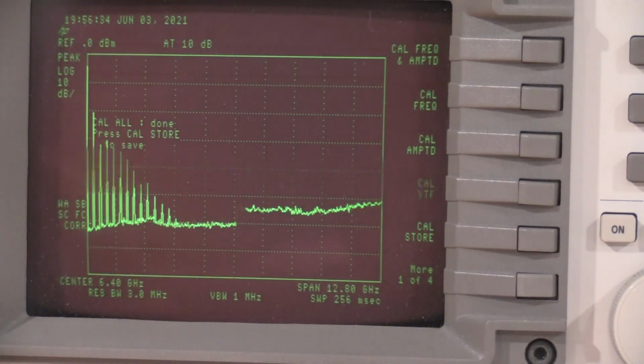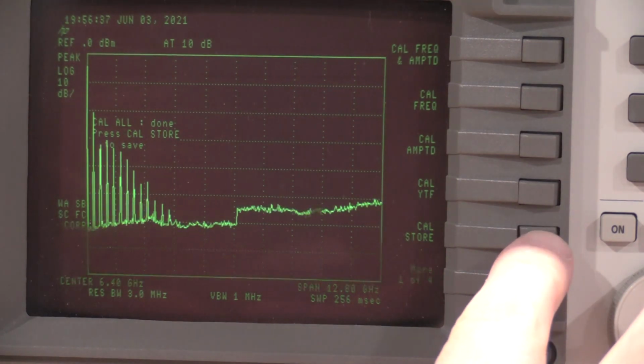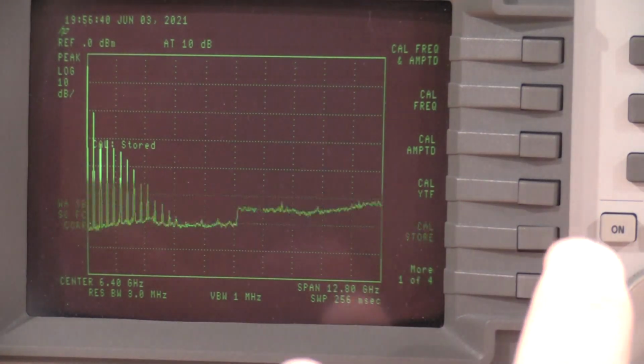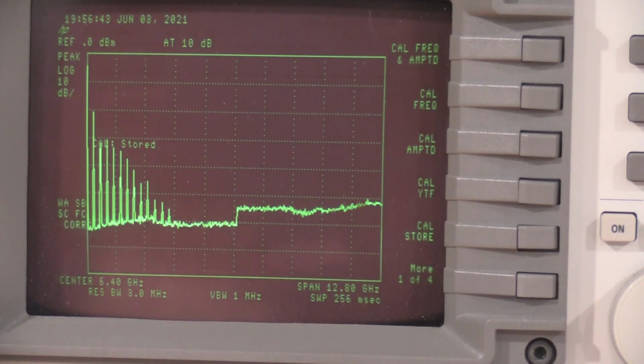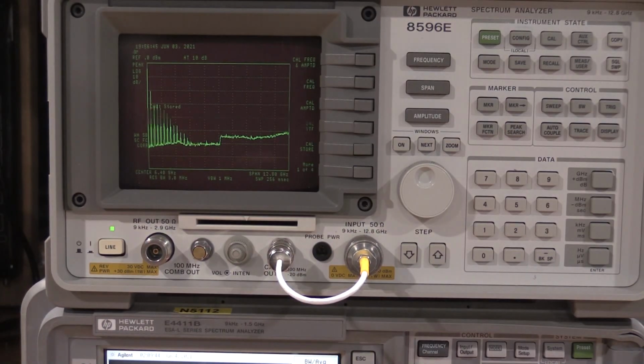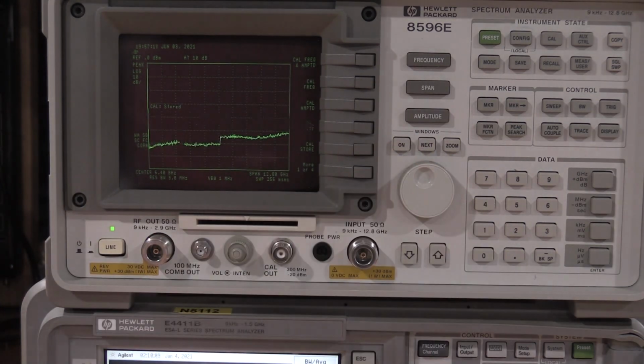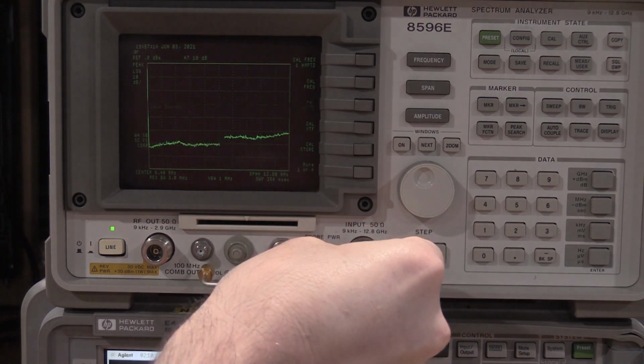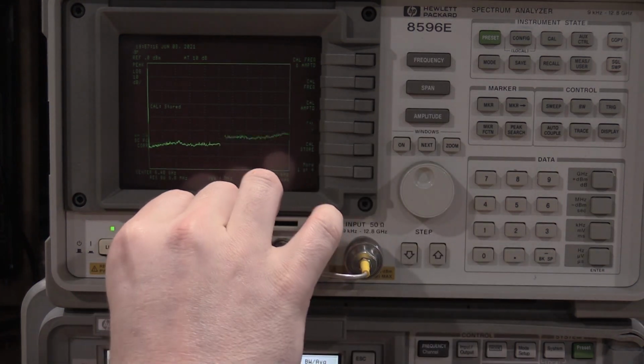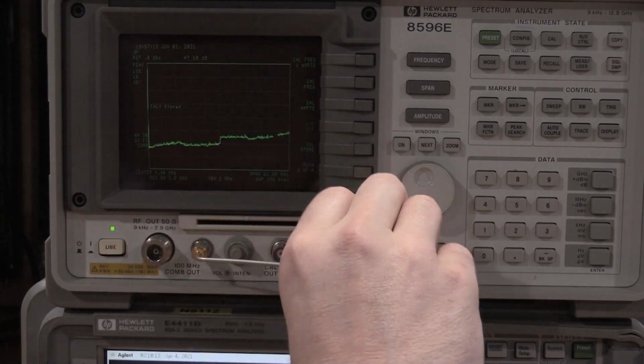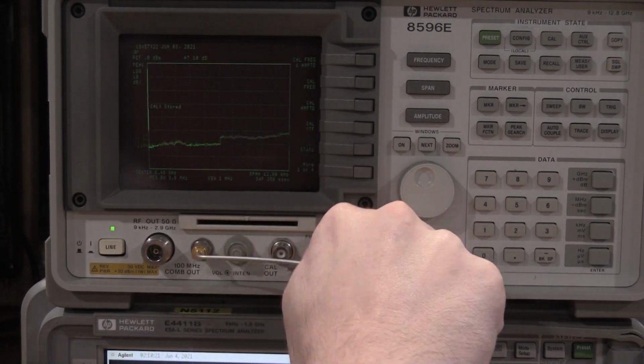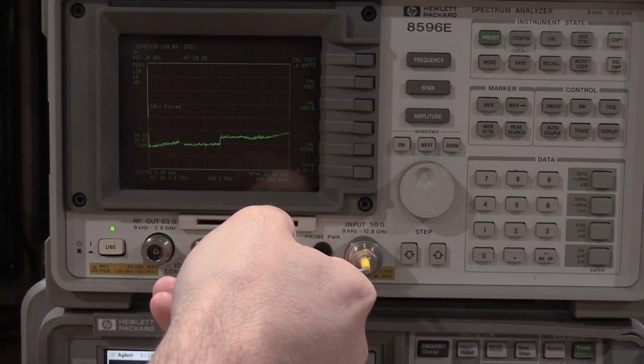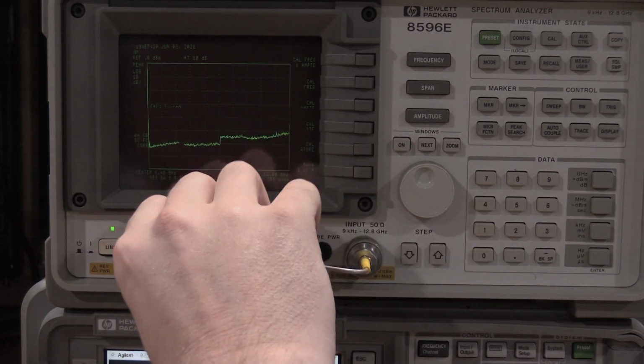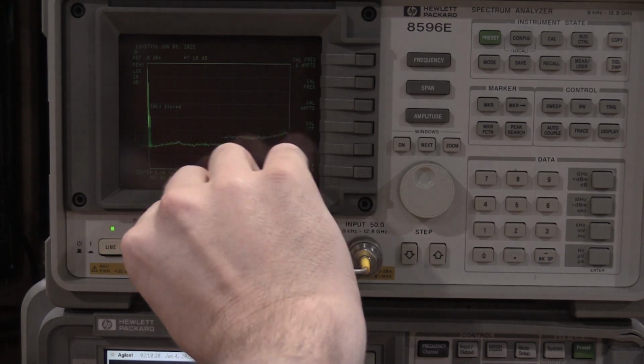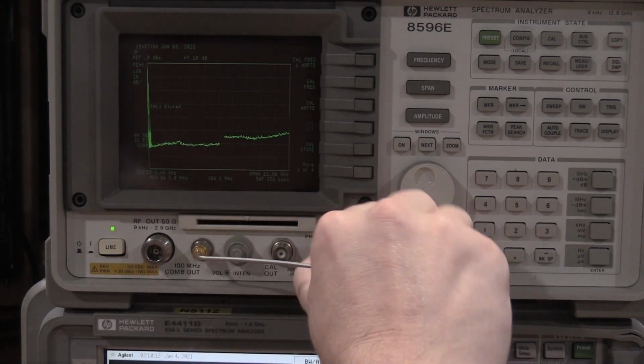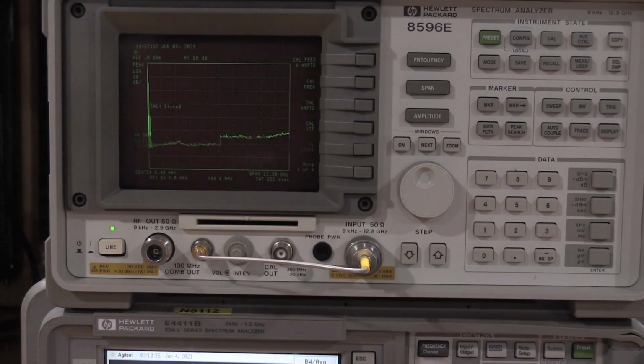As we can see, it says Cal all done. Press Cal store. Cal stored. Now what I need to do is use the other Cal cable, and I need to expose the comb out. And you want to be real careful with this cable. You want to kind of put the connectors in at the same speed, a little bit on one, and you really don't want to bend this cable. This is a hardline coax. All right, everything's in.